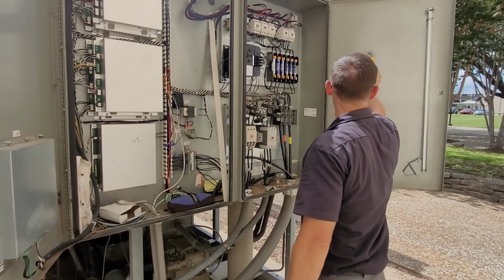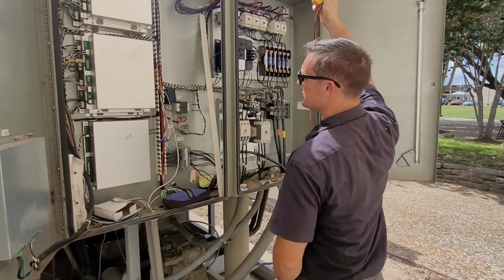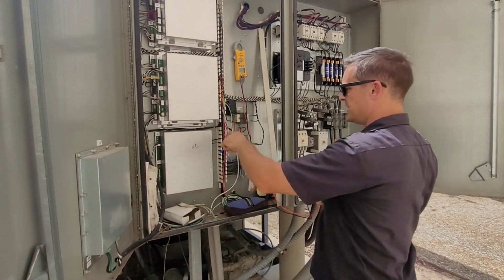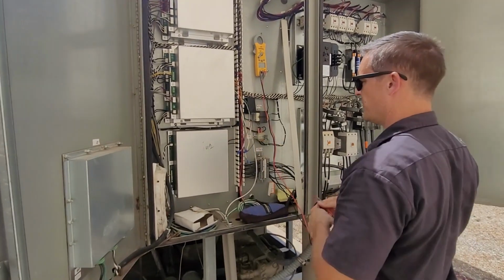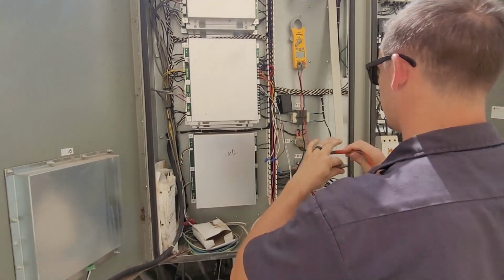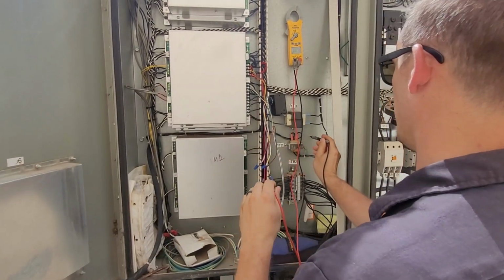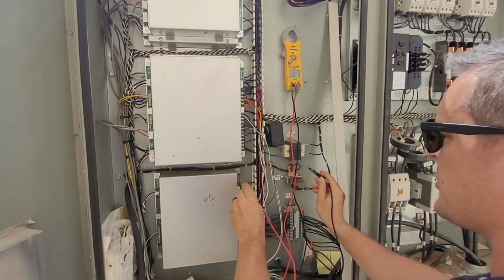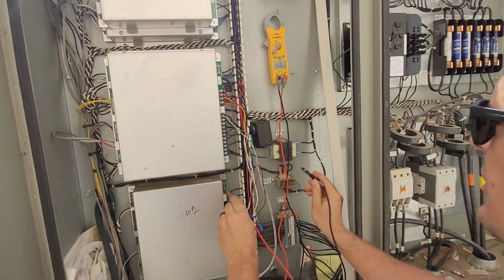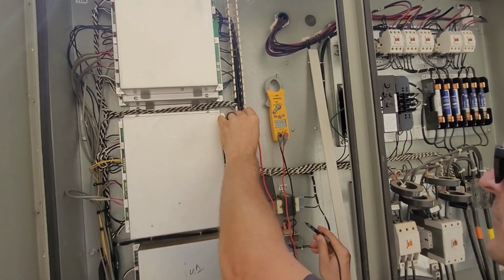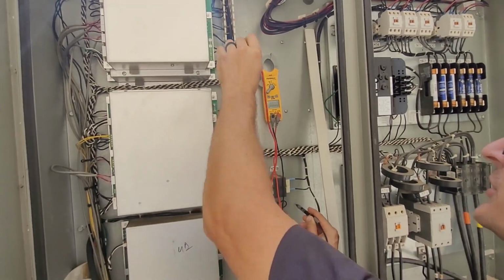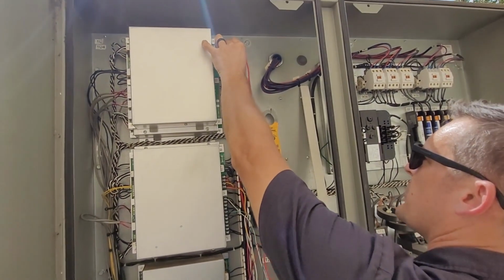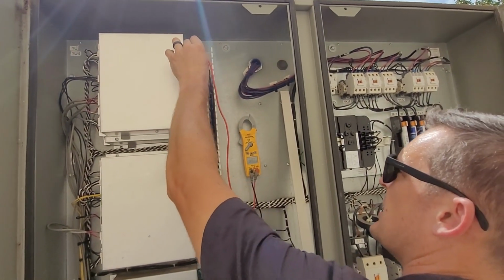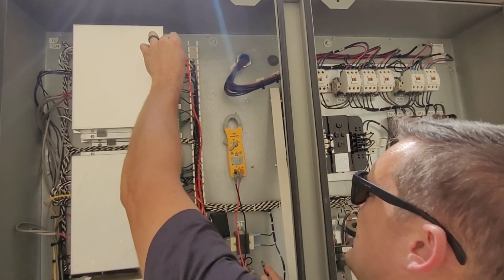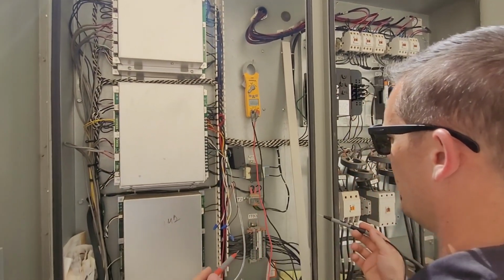But the first thing I did was I started looking for fuses. And I see fuses on these boards, 115 volt it says. So I set my meter to AC and I'm going to ground and I'm checking around here. All the fuses look good and there's no power on either side of the fuses anywhere, no power anywhere. So that 115 volt power source is just dead. So it's a high voltage problem, not a low voltage problem.